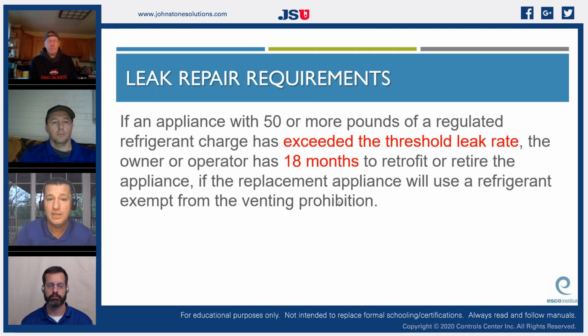If an appliance with 50 pounds or more of a regulated refrigerant charge has exceeded the threshold rate, the owner or operator has 18 months to retrofit or retire the appliance if the replacement appliance will use a refrigerant exempt from the venting prohibition.